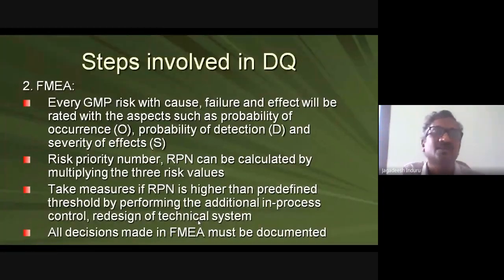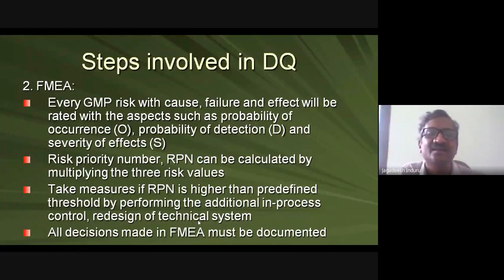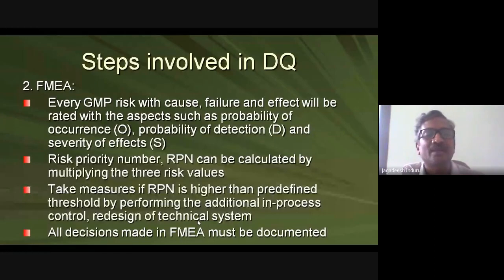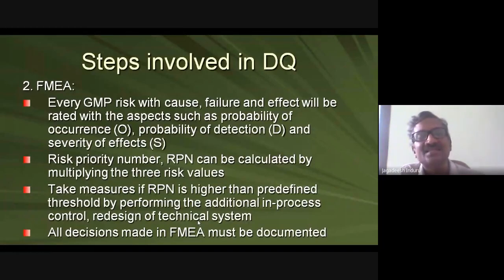In FMEA, every GMP risk with cause and failure effect is rated using three factors: probability of occurrence (rated say one to ten), probability of detection, and severity of effect on GMP. You multiply all three to get a Risk Priority Number (RPN). The factor with the highest RPN must be considered first. If RPN is higher than the threshold, the deficiency must be resolved by performing additional in-process controls or redesigning the technical specifications.